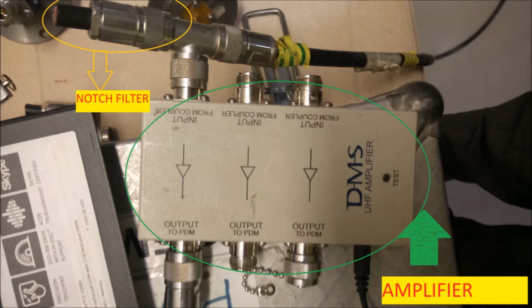Secondly, the input which comes from the PD coupler is passed through a notch filter before it enters the kit, as noise will always be there in the substation and we have to somehow cancel this. So basically a notch filter is used for that purpose. Then lastly, the cable end which is connected towards the PD coupler is equipped with a surge arrestor to prevent the kit from getting faulty due to high voltages.